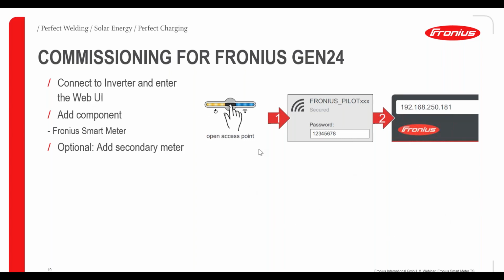On the Gen 24 models, because we don't have any display on the inverter, we simply click on the button on the front side of the inverter, and this way we activate the Wi-Fi access point. Then you go to the Wi-Fi settings of your device, and you choose the Fronius network. You enter the password. That's the standard password for all of our inverters from 1 to 8. After that, if you're using your computer, you go into your browser and enter this IP address. And after that, you get into the web interface of the Gen 24 inverter. If you're using the Solar.start app, after activating the Wi-Fi access point, you will be automatically redirected to the web interface of the inverter.